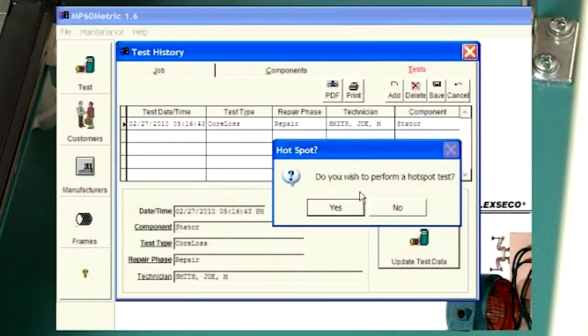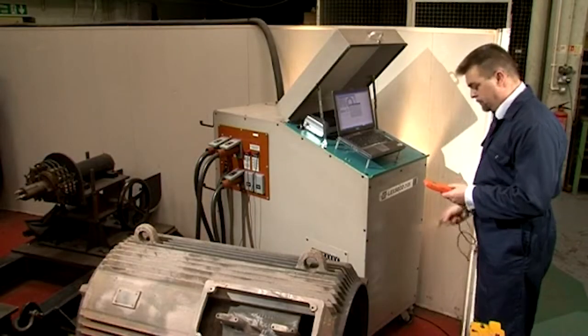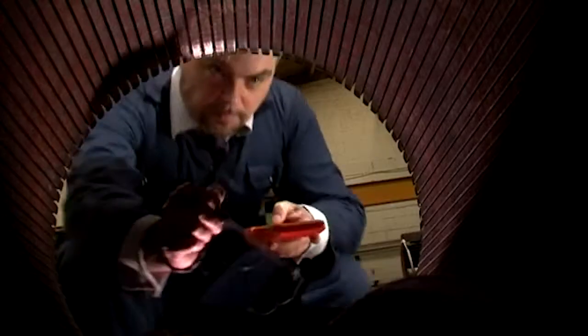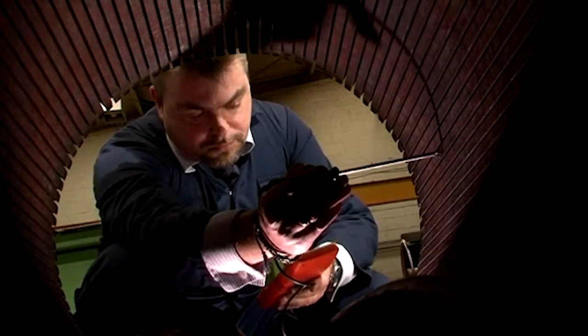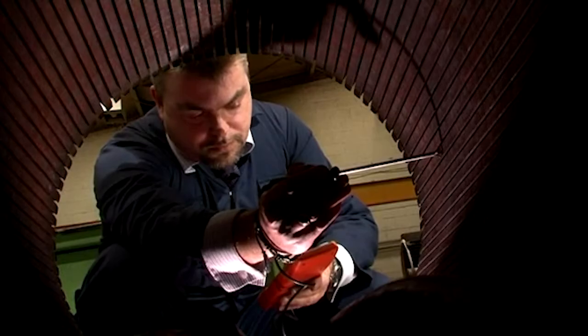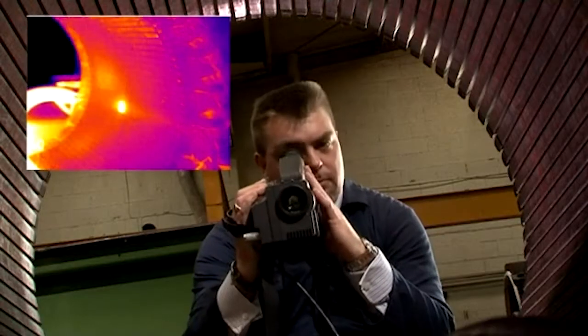Lexseco core loss testing can then be applied to check for any localized areas of degradation once the test for average core loss has been carried out. This can be done in conjunction with a contact temperature probe, any suitable non-contact thermometer, or a thermal imaging camera.